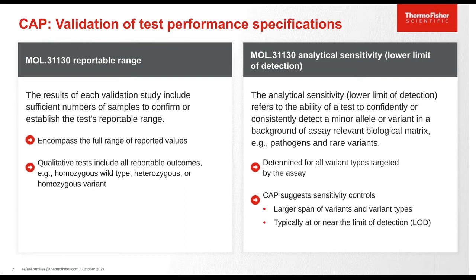Each validation study must include sufficient numbers of samples to confirm or establish the test reportable range, encompassing the full range of reported values. For pharmacogenetic studies, you need to cover all potential reportable outcomes such as homozygous wild type, heterozygous, or homozygous variant for all assays on your panel. Analytical sensitivity or lower limit of detection refers to the ability of a test to confidently detect variants in a background of assay-relevant biological matrix. You need to spike your control material into your intended sample types such as urine or swab media to take through your extraction, and include multiple biological and technical replicates throughout the qPCR process.